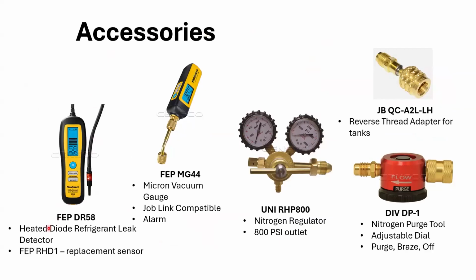Accessories. So, refrigerant leak detector, right? We're into 454B, so make sure your tools are capable, that the leak detector is capable for that. Separate micron gauge, right? Not using the micron gauge built into your manifold set. Those get contaminated with oil, and then they don't read correctly.